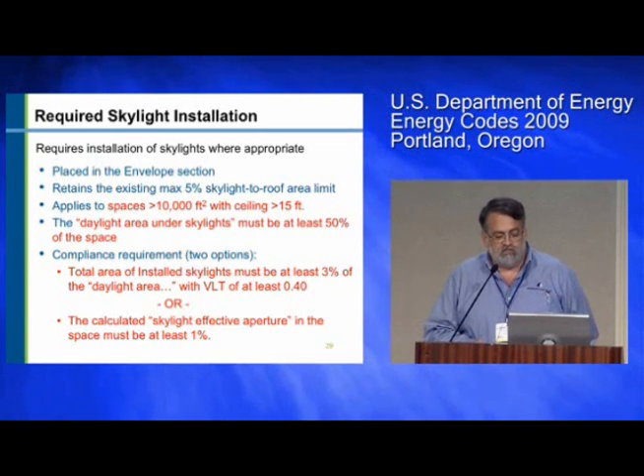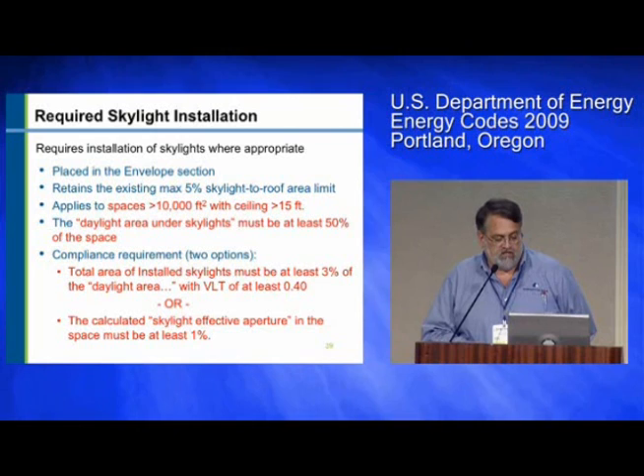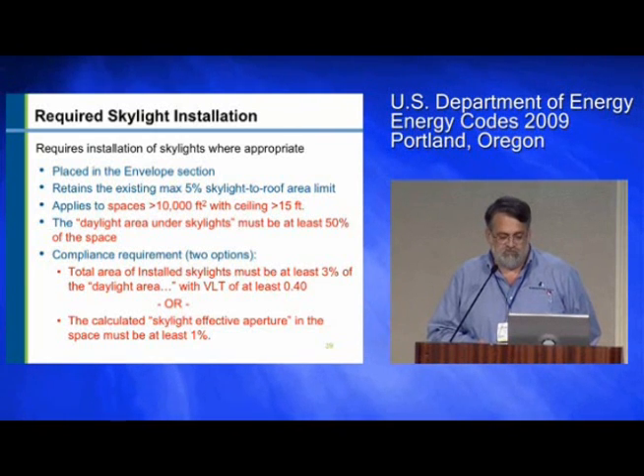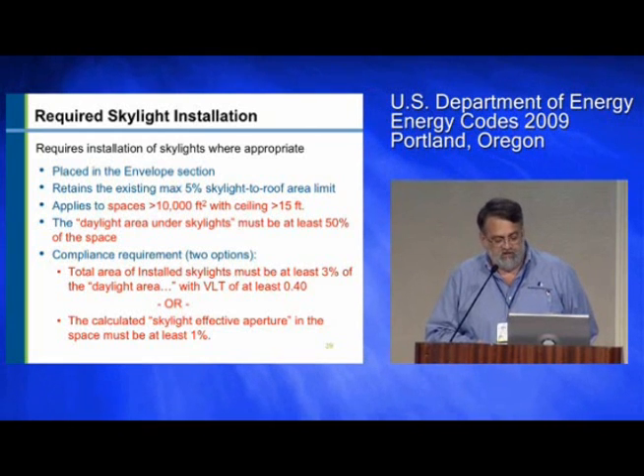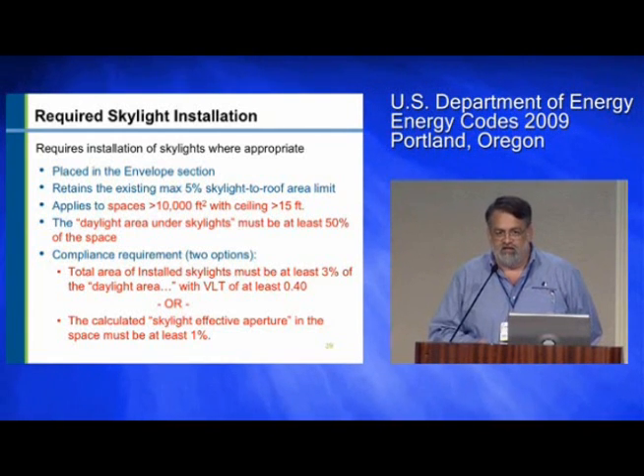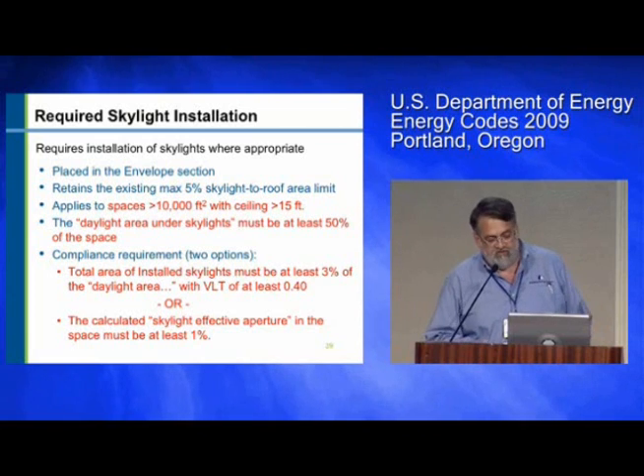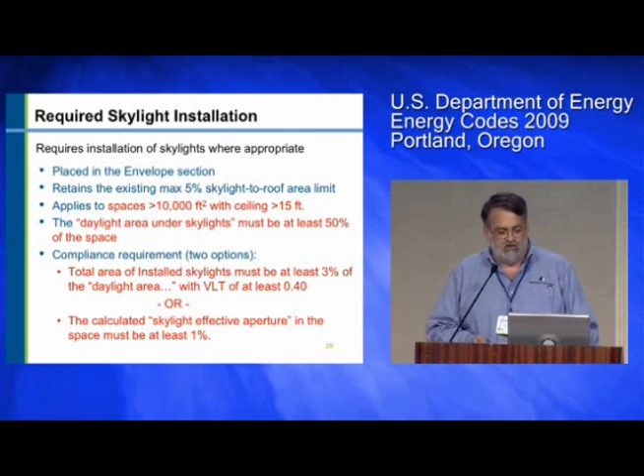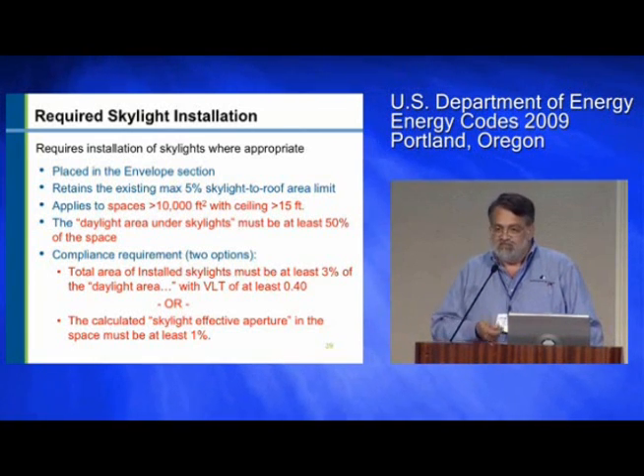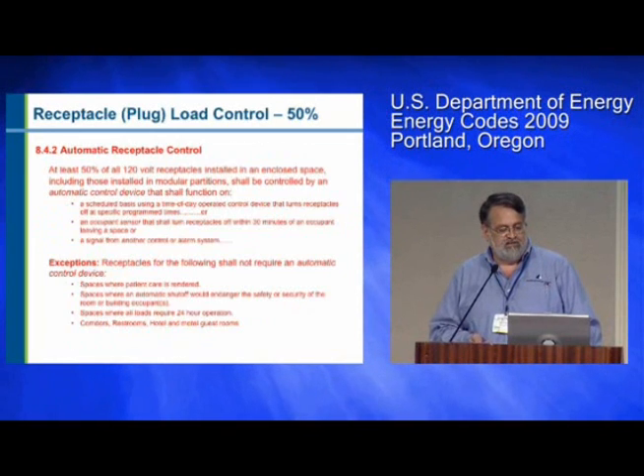The total area of the skylights has to be at least 3% of the daylight area with a VLT, visual light transmittance, of at least 0.4, or a calculated skylight effective aperture that's at least 1%. And again, there's another definition for skylight effective aperture, but I'm not going to go through all those boring details. You can always get details from me later on if you like.